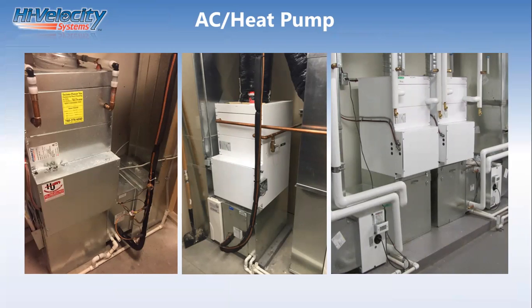Our coils are all heat pump ready out of the box and ready to be installed with any third-party heat pump manufacturer. What I'm showing here is our coil location, which is non-traditional, being on the return side of the blower cabinet. Being a return side cooling coil, we can get considerably more latent cooling, and that's considerably more humidity removal and moisture removal from the air. In high humidity locations, cooling just the sensible temperature of air can lead to clammy conditions within a home. Having properly sized air conditioning equipment will also remove the latent content, the moisture content from the air within the structures, providing a much more comfortable feeling to the occupant.